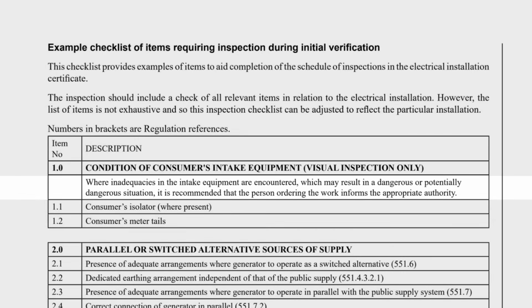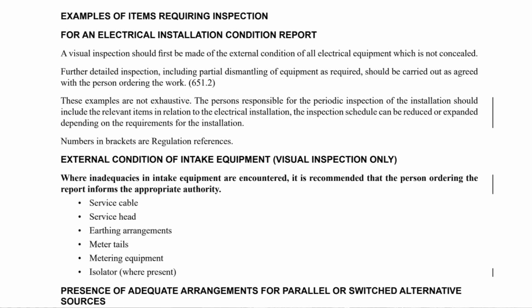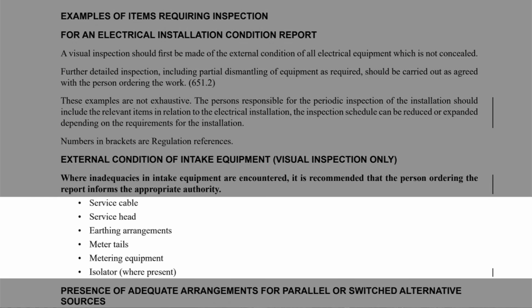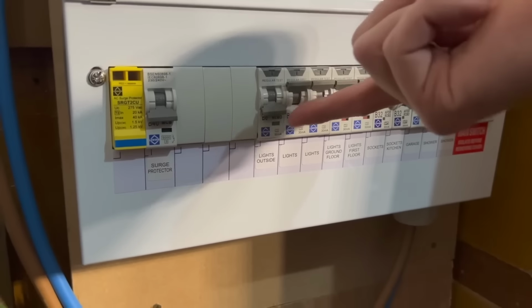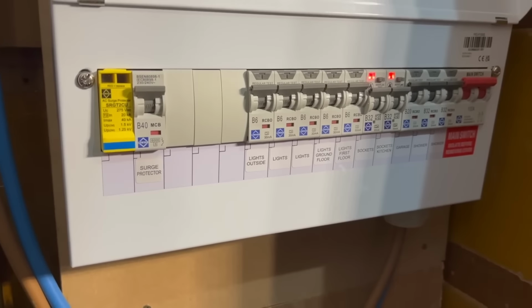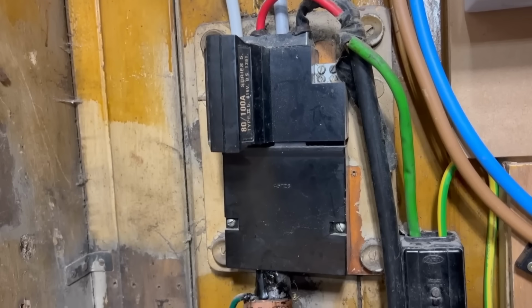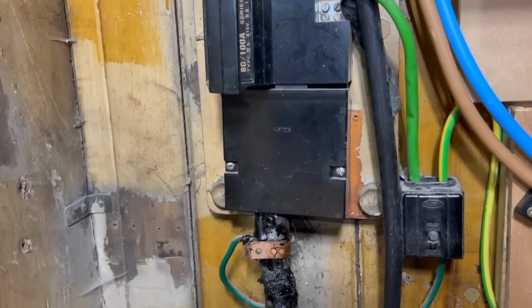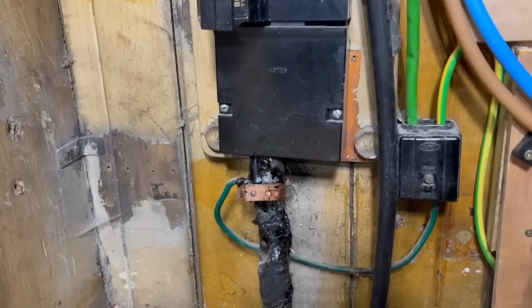It's a little more expansive in the periodic inspection section, suggesting that we inspect the service cable, the service head, the earthing arrangements, meter tails, metering equipment, and the isolator where present. So there's a slightly broader range of things suggested there. However, it makes sense to apply the longer list on initial verification anyway. After all, a rewire or a refurb could require connecting to an older intake system. Either way, if you find anything within these categories that isn't right, then it's time to contact the DSO and get them to come and fix it.